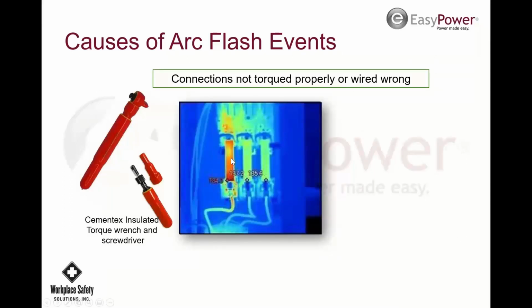Infrared testing is a good thing. So this just says this was actually over torqued. You have to torque your electrical connections to make sure they're proper. Over torquing is just as bad as under torquing. So you use a torque wrench or torque screwdrivers to do your electrical connections.